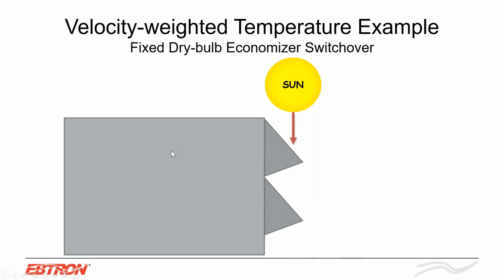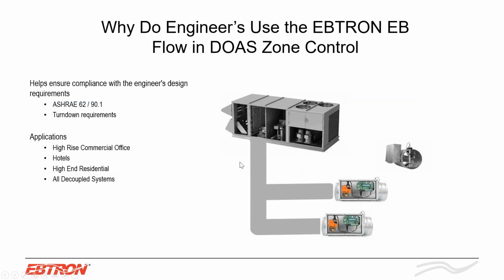Now, let me just go to this. We also have more application-specific products. So for DOAS systems, we have a smaller unit, which is called the EBFlow unit. And why do engineers like to use this? Well, if you have a DOAS system going to single zone, say it's a classroom, you can measure at the terminal unit with the EBTRON units, and you can control the air going to that space. This helps you meet 90.1, which is the energy standard if you're having turn down requirements in your system, because the EBTRON units, again, can read at really, really low flows and can read accurately. So now you have an extremely high performance, basically VAV control box with the EBTRON units. These are just some type of applications to think about, high-rise commercial offices, hotels, and any type of decoupled system, you can use the EBTRON product.